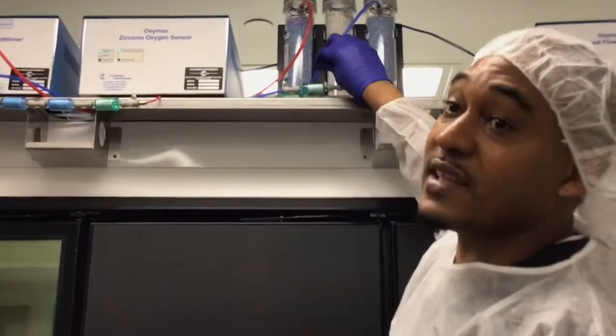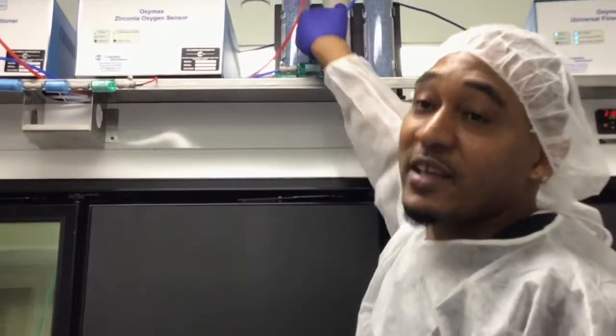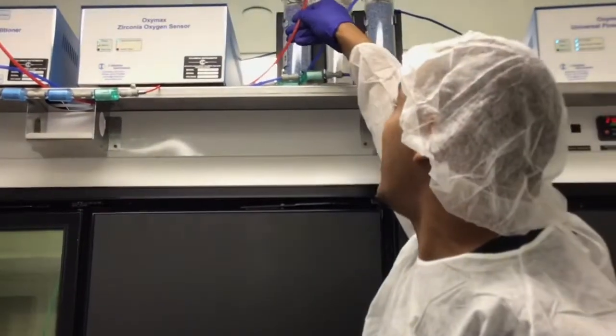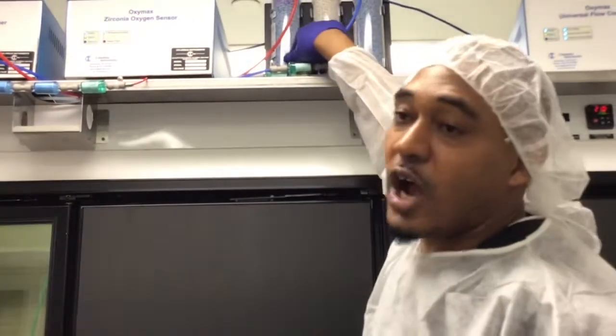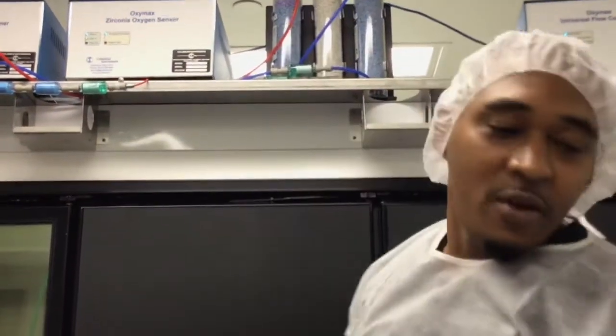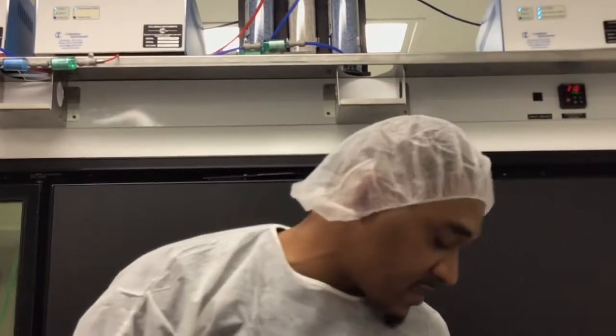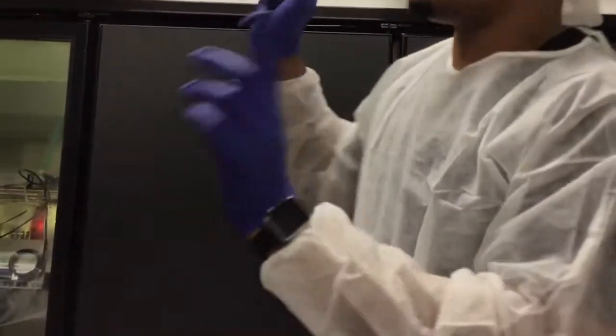So what we do is we draw the sample. Is the sample itself being dried? Yes, it's being dried, but does the sample go through the dryer? No. Actually, we have a system to do that. It's like two tubes, an inner tube and an outer tube. Your sample is never corrupted. Your sample never goes through this.